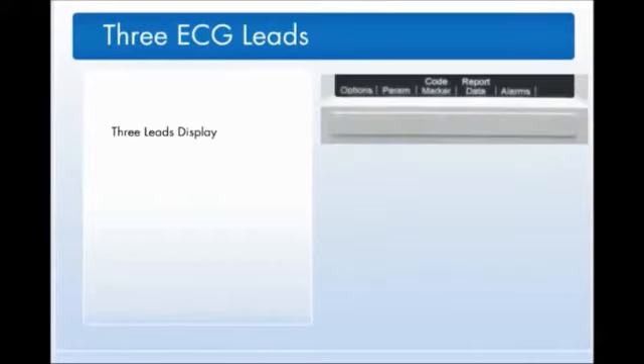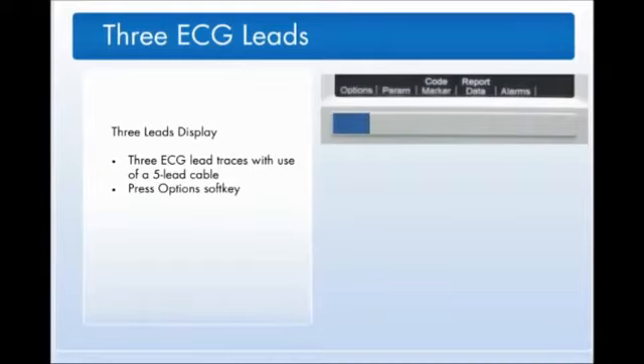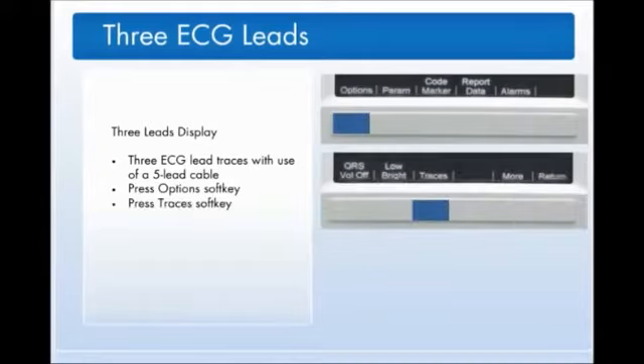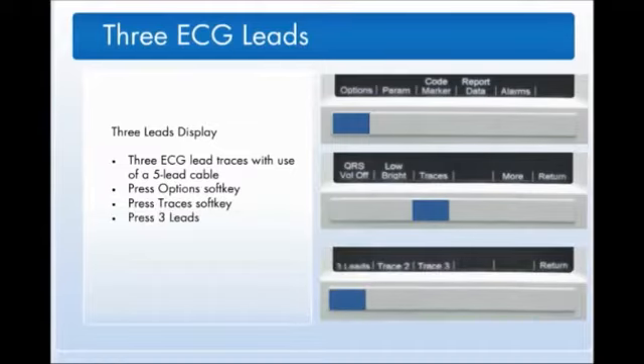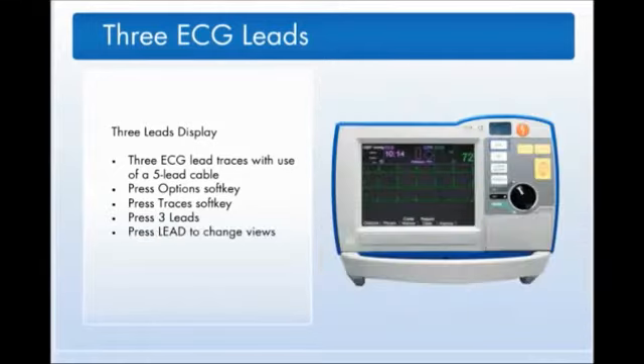The R-Series can display three ECG lead traces with the use of a 5-lead cable in monitoring mode. Press the Option soft key. Press the Traces soft key, and then press the 3 leads soft key. Press the lead button to change the views.